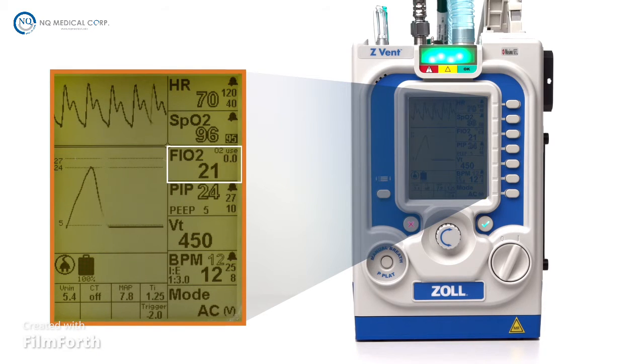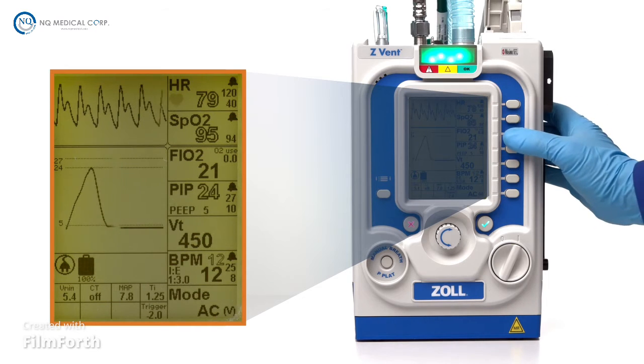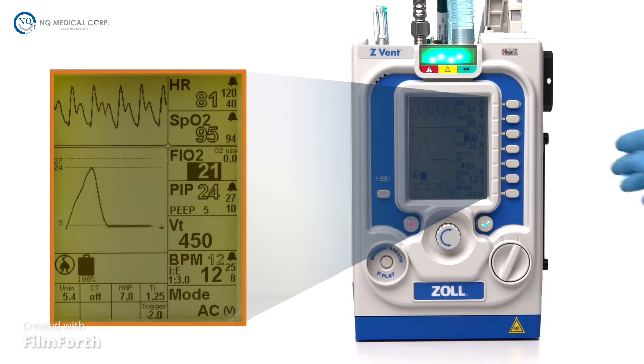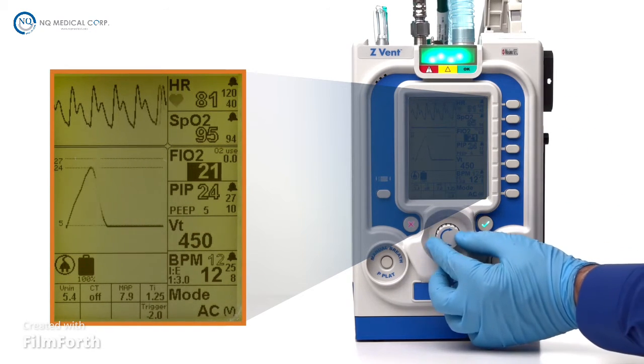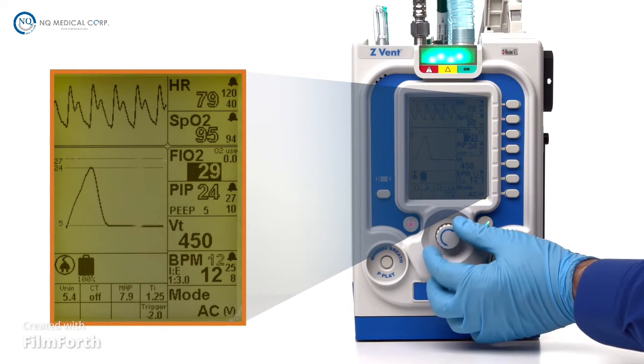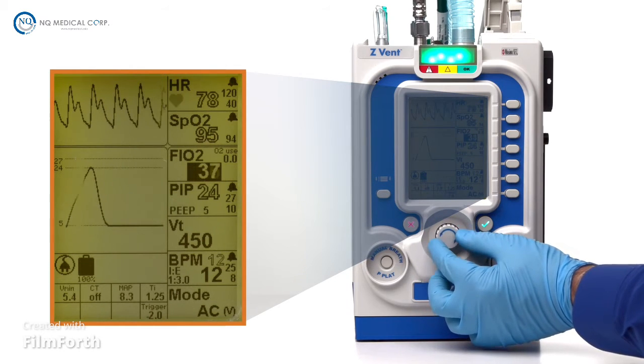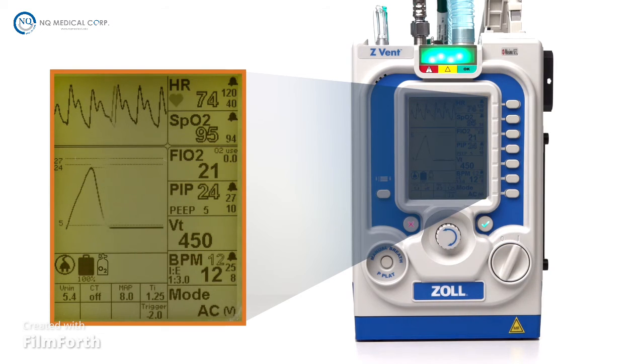The third window is fraction of inspired oxygen percentage, or FiO2. The desired FiO2 can be adjusted in 1% increments from 21 to 100%. Press the parameter button once to change the desired FiO2 level.